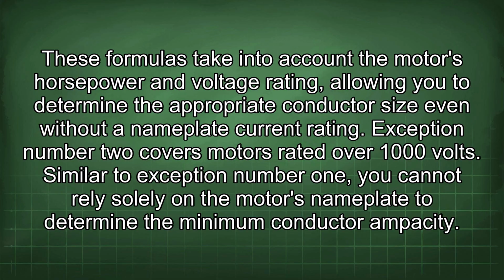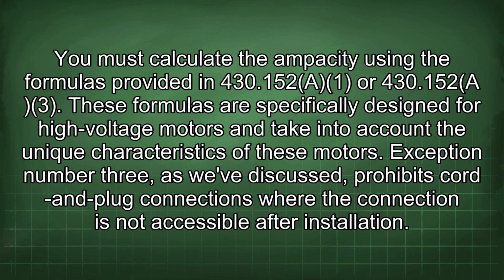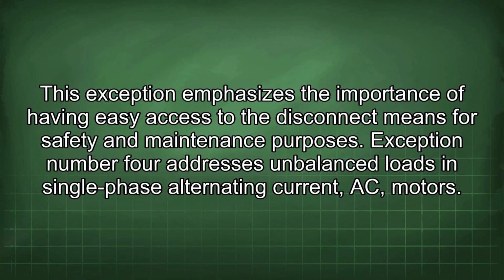Exception number 2 covers motors rated over 1000 volts. Similar to exception number 1, you cannot rely solely on the motor's nameplate to determine the minimum conductor ampacity. You must calculate the ampacity using the formulas provided in 430.152. These formulas are specifically designed for high voltage motors and take into account the unique characteristics of these motors. Exception number 3, as we've discussed, prohibits cord and plug connections where the connection is not accessible after installation. This exception emphasizes the importance of having easy access to the disconnect means for safety and maintenance purposes.